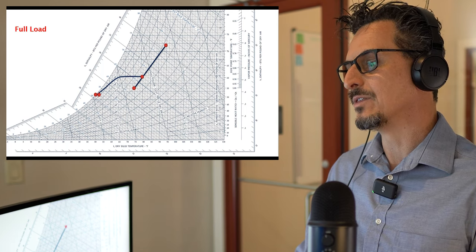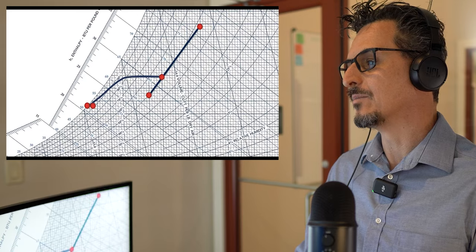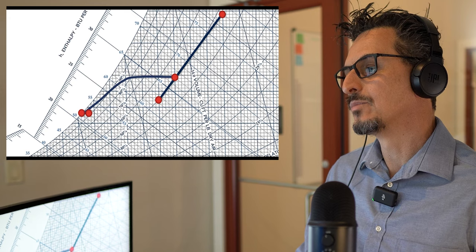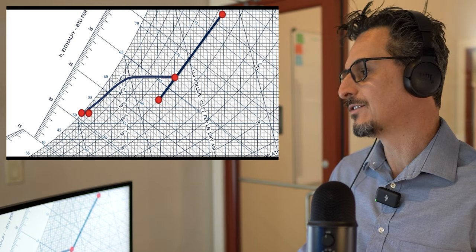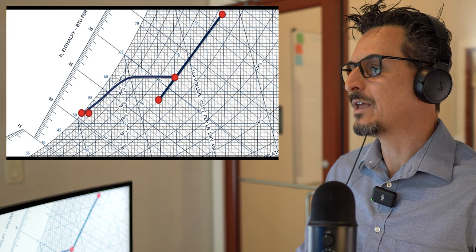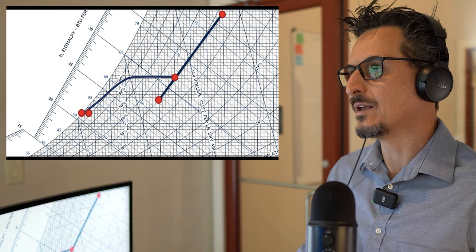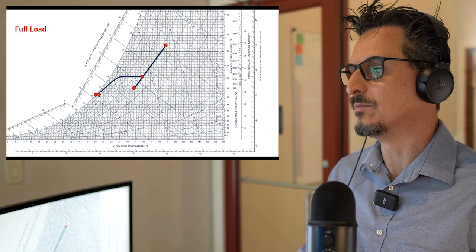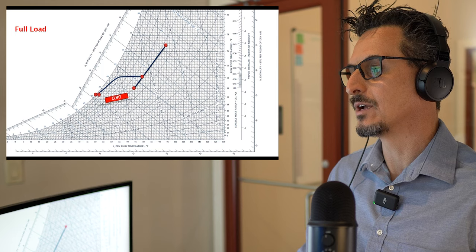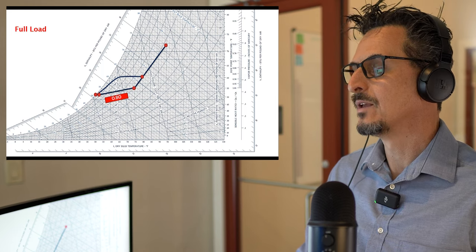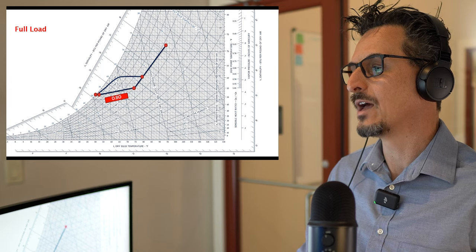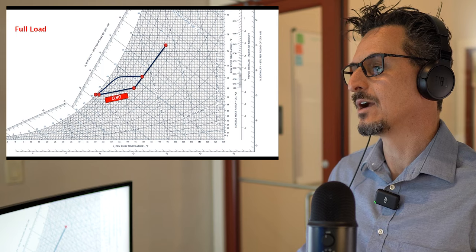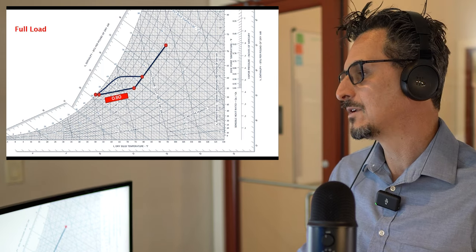We have two degrees of heat pickup — one for the fan, one for the duct — and then we end up at 53°F entering the space. This air should be at the correct proportion of dryness and coolness such that it will hit the SHR, absorb the heat and moisture in the right ratio, and result in the desired room design — 75°F, 50% RH at a 0.8 SHR.